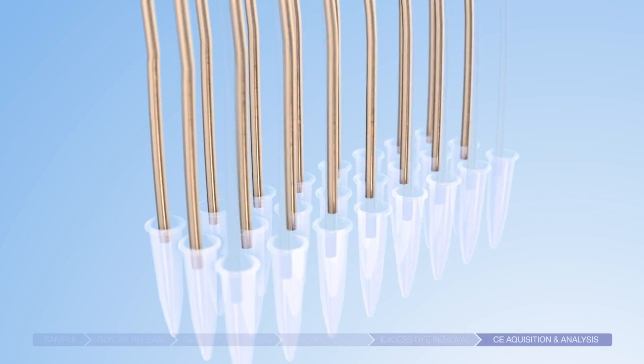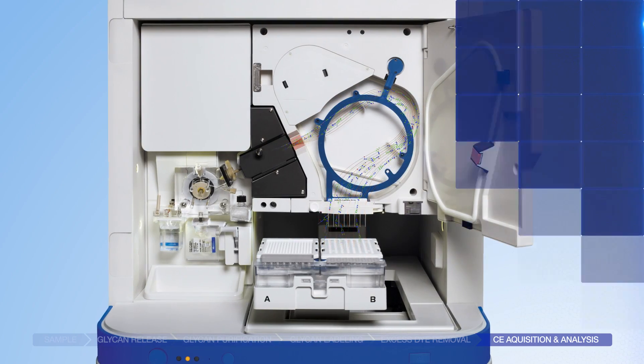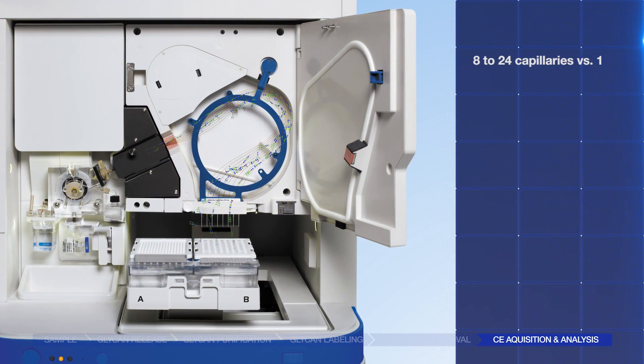The fully integrated separation platform allows for up to 24 capillaries, in contrast to traditional single capillary systems, and enables high throughput with high resolution separation. This helps improve the assay throughput and overall data quality.